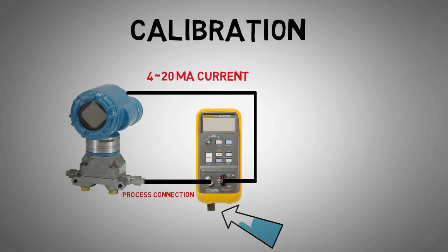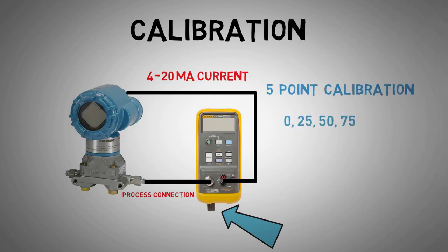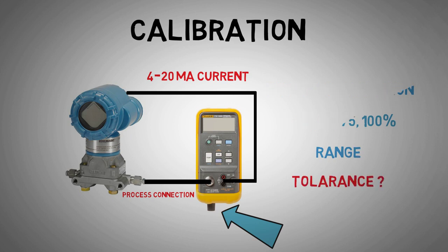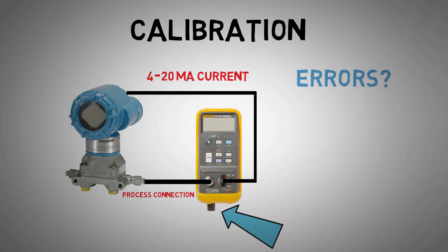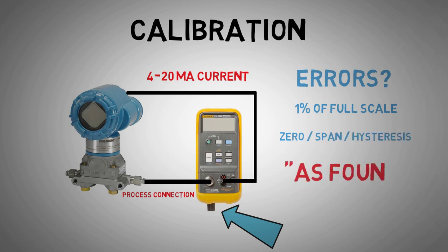We would then apply various test pressures along the range of the transmitter and record the values on a calibration certificate. In a 5-point calibration, we will often be testing 0, 25, 50, 75 and 100% of the range of our transmitter. We would work out if the transmitter is within the required accuracy for a specific piece of equipment. Something like 1% of range maximum error is usual for general purpose pressure transmitters. We would also check for zero, span and hysteresis errors. This is called the as found test.